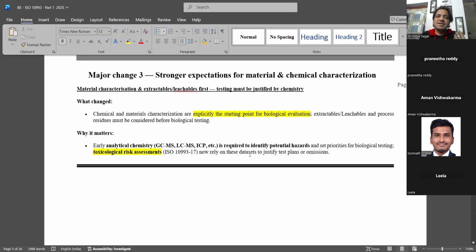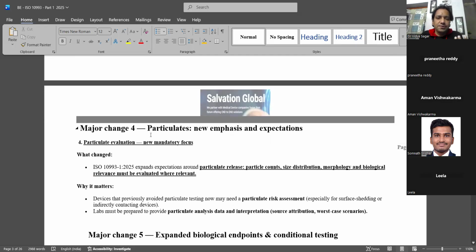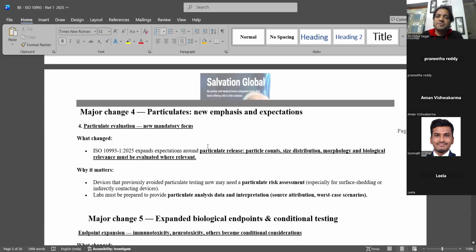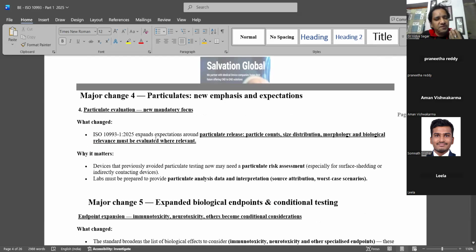So major change 3 is you need to do material and chemical characterization. This I told you, particulate matter, this is something new. You need to have a new SOP, or it has to be included in your BEP, because you need to tell for anything that comes in contact with skin, with the human body. Expand expectations around particulate release, whether the particulate matter is getting released or added to the device. Okay, particle count, size distribution, morphology, and biological relevance must be evaluated where relevant.